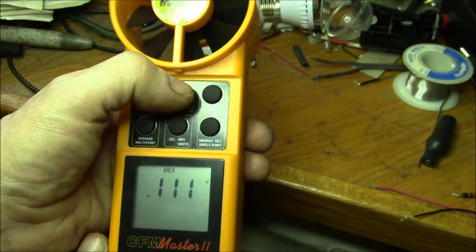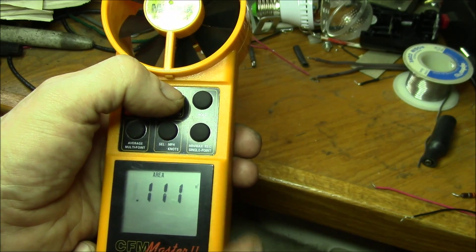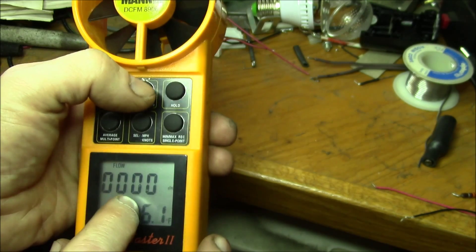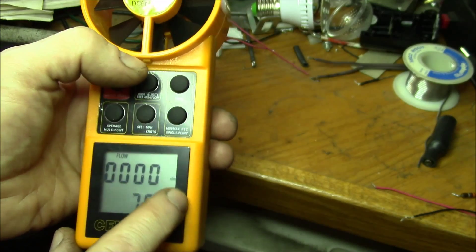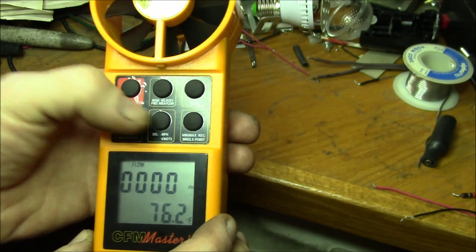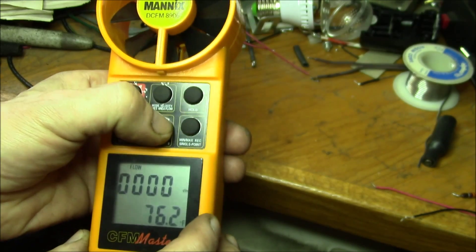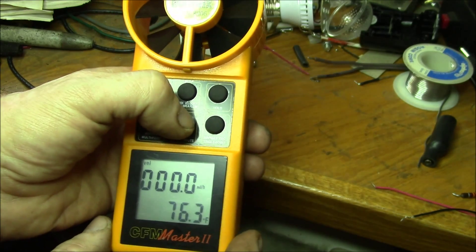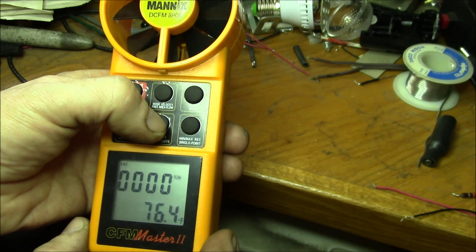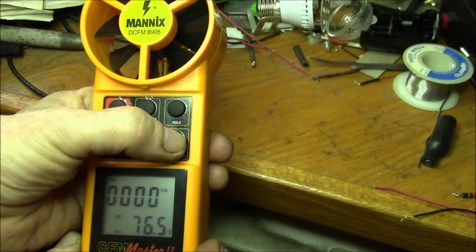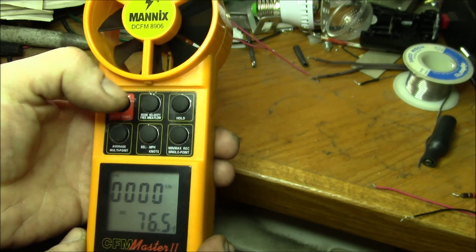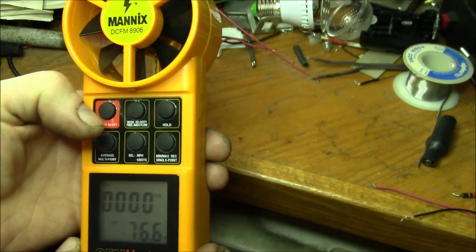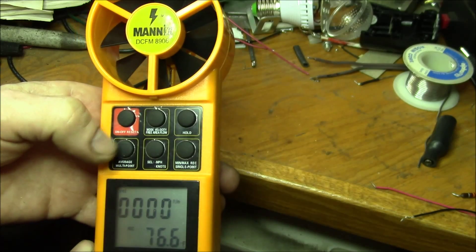You can program the area of the duct or fan you're looking at in square feet, and then that changes to a flow rate. It'll tell you cubic feet per minute. You can change from feet per minute, you can get miles per hour, you can get knots and feet per minute. You can get average and peak, minimum, maximum, and average. There's a hold.